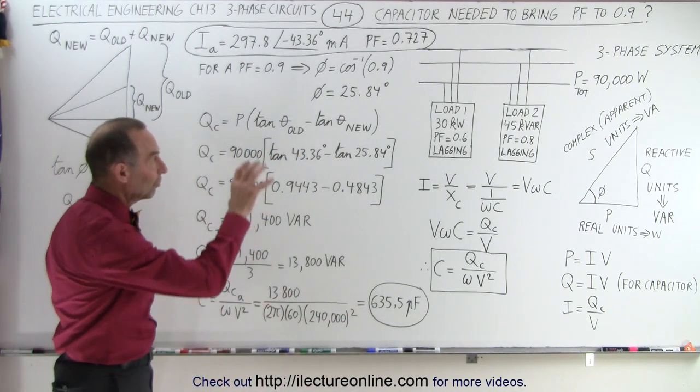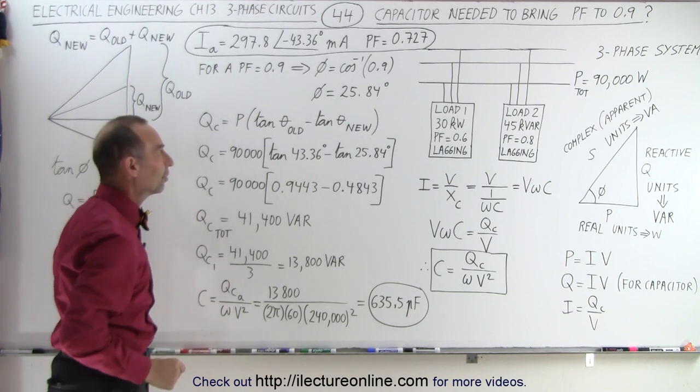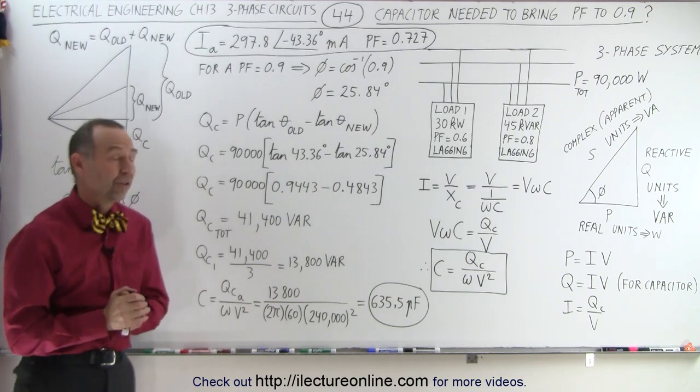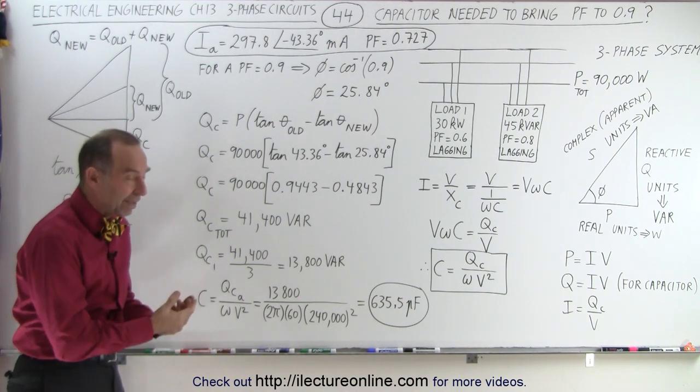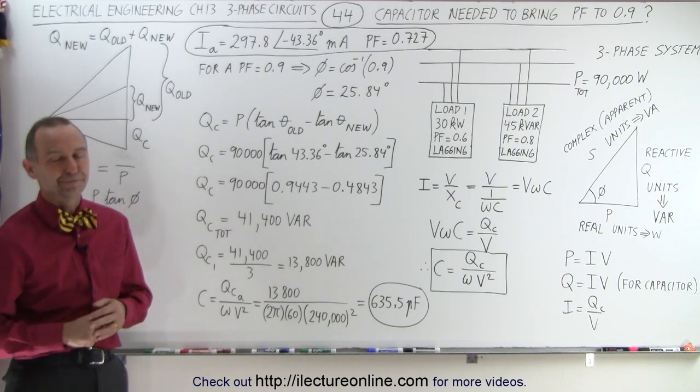If we add that capacitance to the three-phase system, we will increase the power factor from 0.727 to 0.9, and that's the methodology we use to find what capacitor we need to add to the circuit to get the power factor we want. That is how it's done.